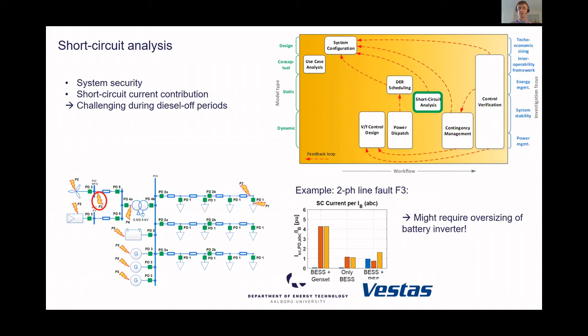And I'm just highlighting, for a specific fault in the system, that with the genset in operation, you reach quite high current levels. This is shown in per unit levels, relevant for a protection device to actually trigger on the fault. And if you disconnect the genset, you have very low short circuit current. So you might need to oversize, for example, the battery inverter just to cope with these requirements, which also has an effect on the cost in the first place.